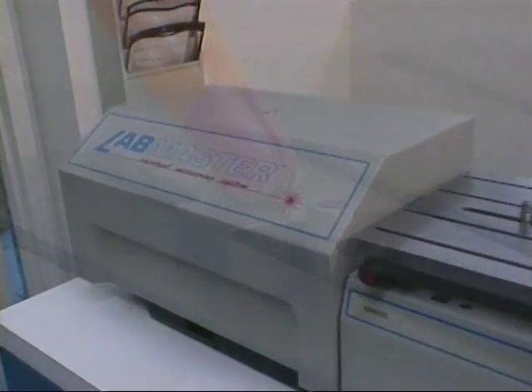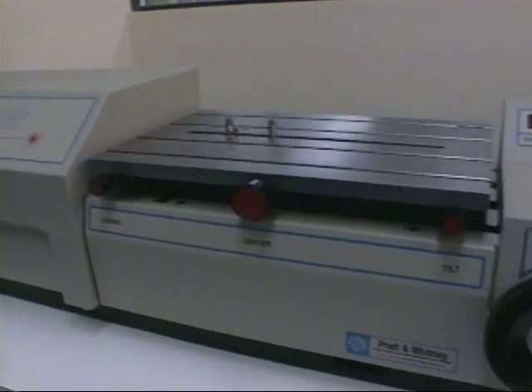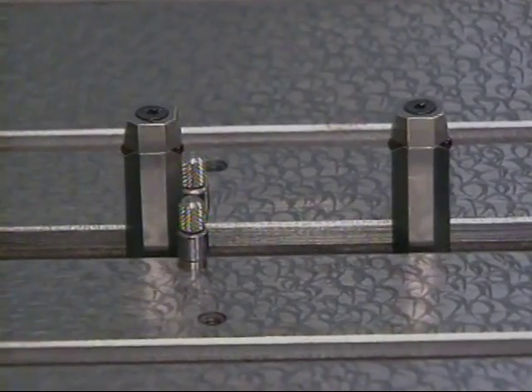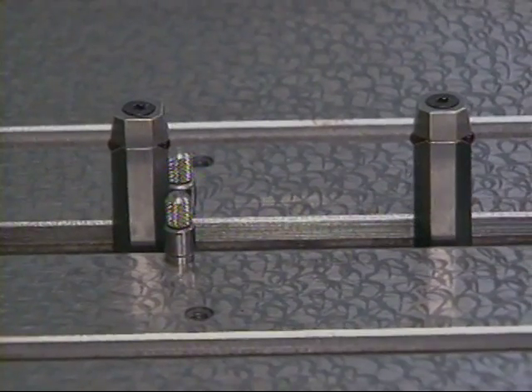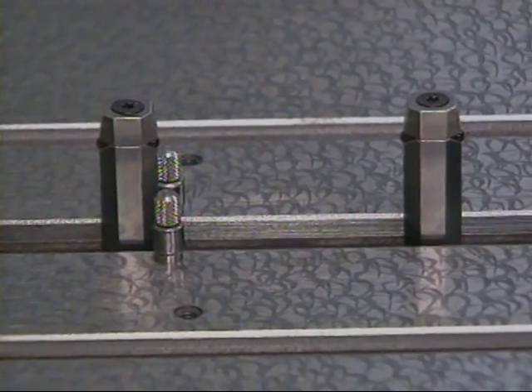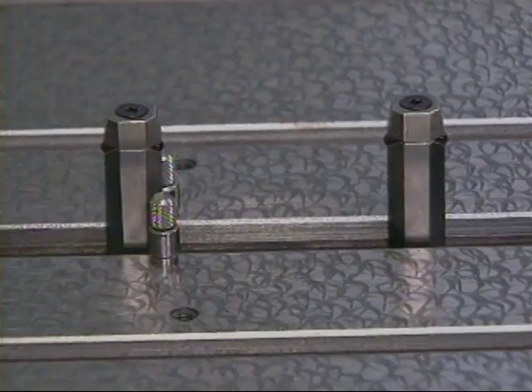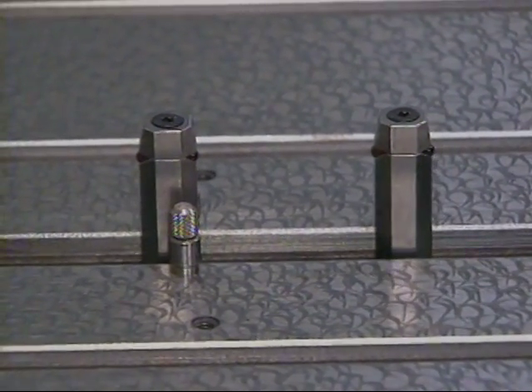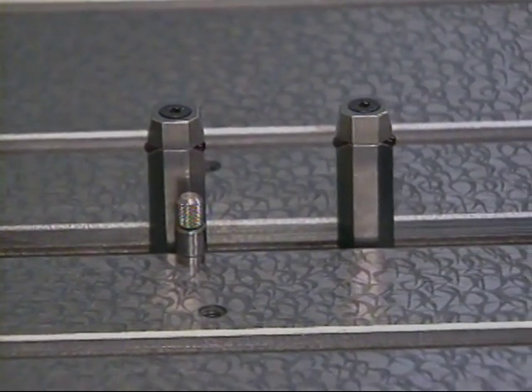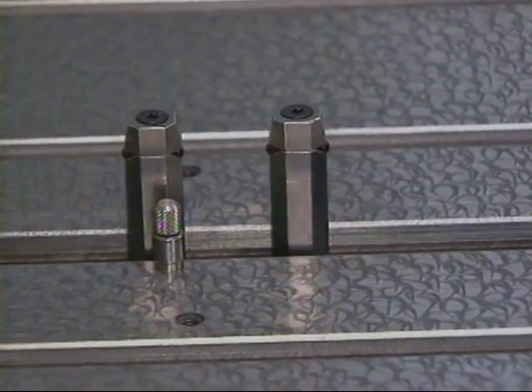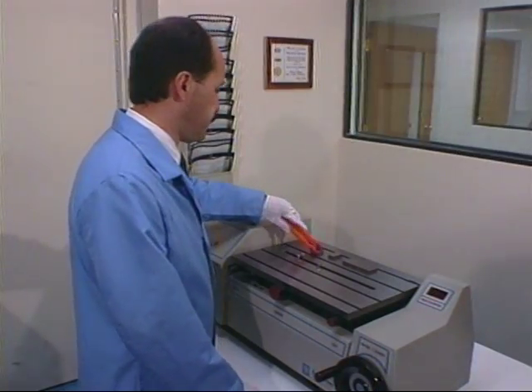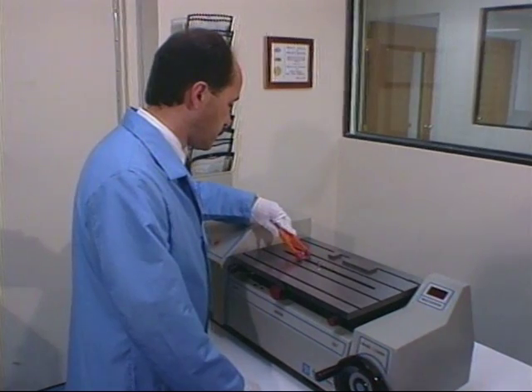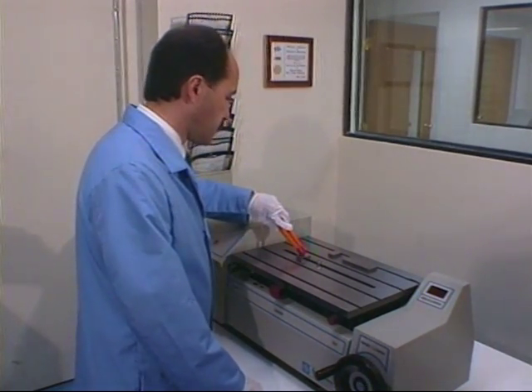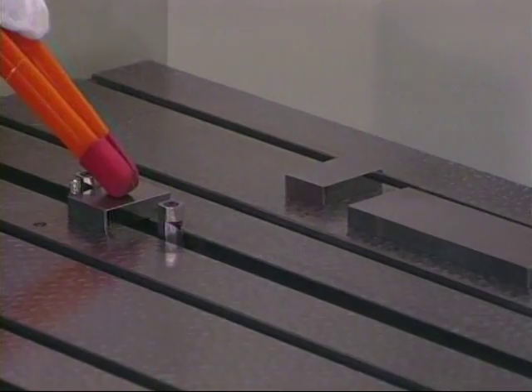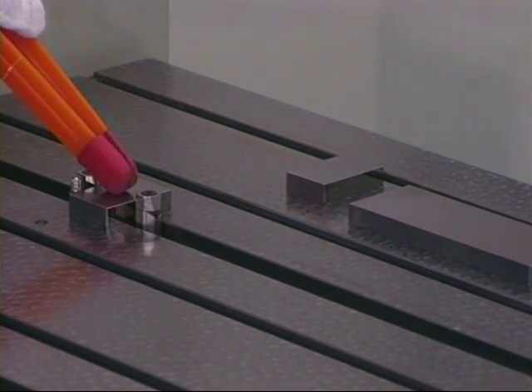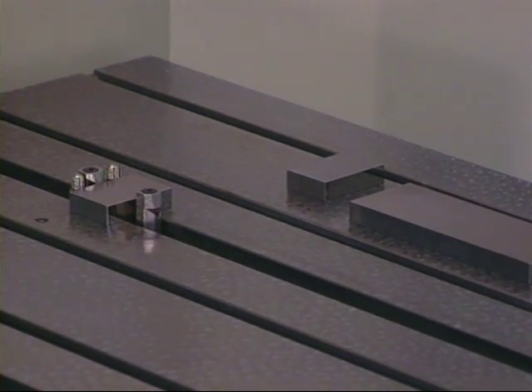The LabMaster is constructed of thermally stable composite materials. Its exclusive bidirectional probes offer a wide direct reading range that reduces time-consuming setups. These probes and associated optics travel along very accurate air-bearing slides. To master the system, use a laboratory-grade gauge block, traceable to the National Institute of Standards and Technology, known as NIST. Place the block against the integrated locating posts and close the bidirectional probes.